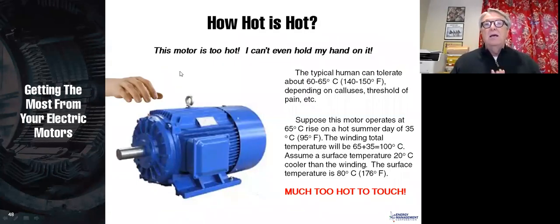Last slide. What if you can't hold your hand on it? Well, a typical human can tolerate about 140 to 150 degrees Fahrenheit or 60 to 65 degrees C. If this motor operates at a 65 degrees C rise and it's rated for 80 on a hot summer day of 35 degrees C and it's rated for 40 degrees C, then the winding temperature is going to be 100 degrees. Assume a surface temperature of 20 degrees cooler than the winding, and then the surface temperature of the motor is 80 degrees, and you are going to find that much too hot to hold your hand on.